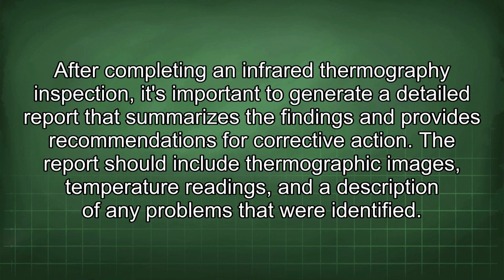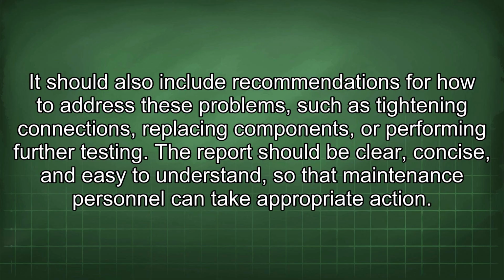After completing an infrared thermography inspection, it's important to generate a detailed report that summarizes the findings and provides recommendations for corrective action. The report should include thermographic images, temperature readings, and a description of any problems that were identified. It should also include recommendations for how to address these problems, such as tightening connections, replacing components, or performing further testing. The report should be clear, concise, and easy to understand so that maintenance personnel can take appropriate action.